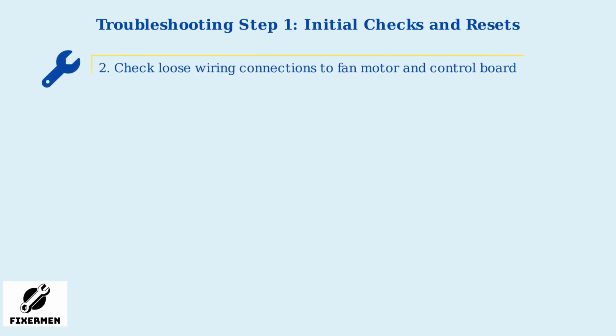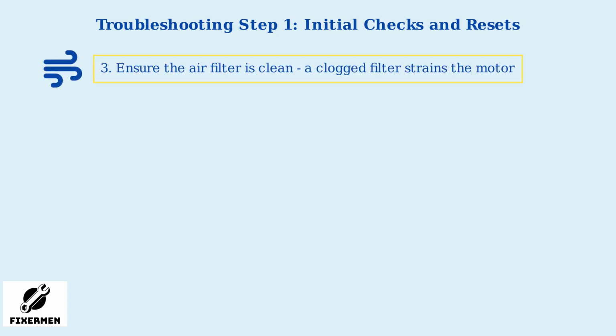Before diving into more complex solutions, start with the basics. First, power cycle the unit by turning it off and on again. This simple step can reset temporary glitches and restore normal operation. Next, check for any loose wiring connections to the indoor fan motor and control board. Loose connections can interrupt the feedback signal, triggering the error code. Ensure the air filter is clean, as a clogged filter can restrict airflow and strain the motor. Regular cleaning prevents unnecessary motor stress.